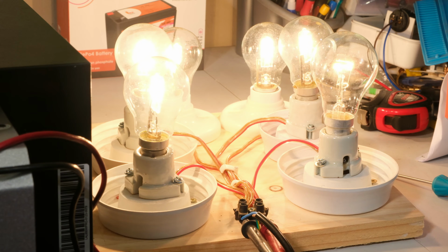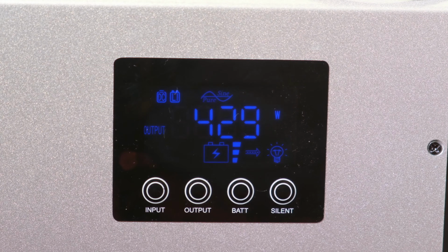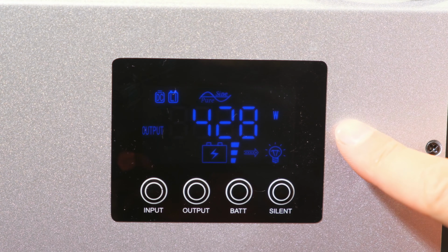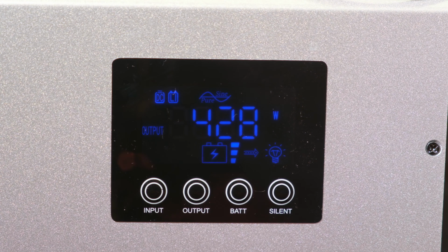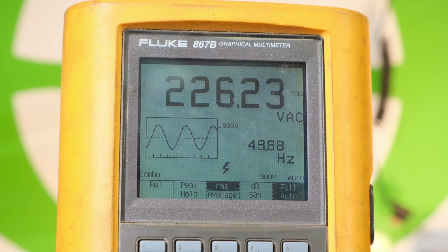I have my loads connected and my meter measuring the voltage coming into the load. According to the inverter, the output power is 427 watts, which is about right. The voltage still says 230 volts, and my meter says 226 volts. The frequency is stable, almost 50 hertz.